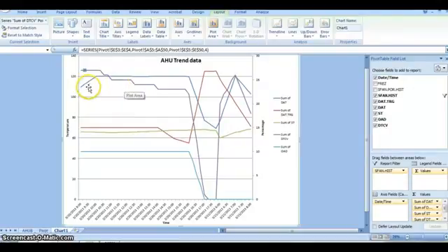and the discharge temperature is staying really high when it should be heating the building. And then the system tends to kick back on around 5:30, 6 o'clock in the morning, and the temperature drops around probably 5 o'clock in the morning, kicks on to keep that temperature up for its occupants again. And you can see the outside air damper doesn't kick on probably until around 8 or 9 o'clock in the morning. That's when kids have to enter the building.